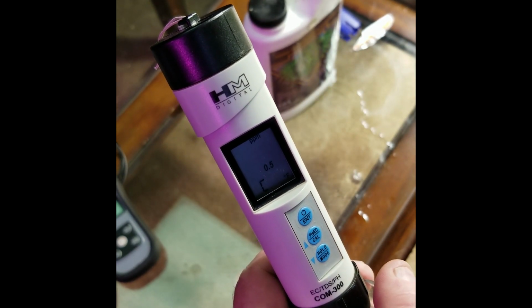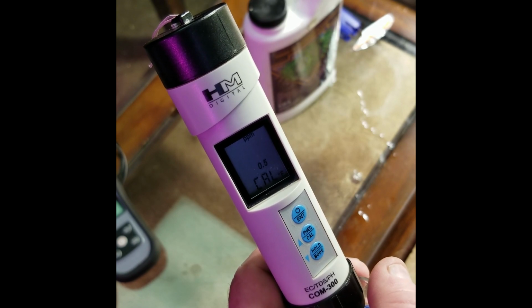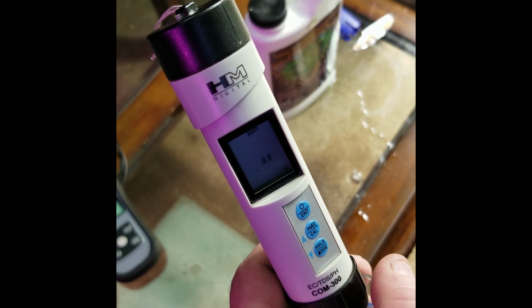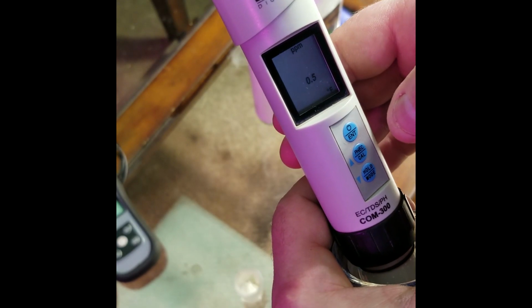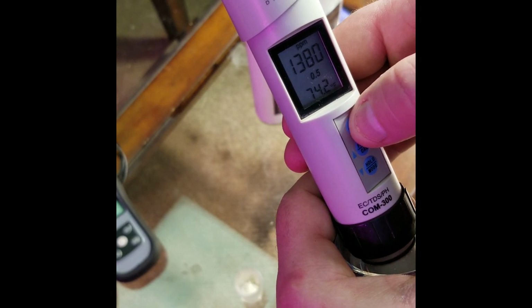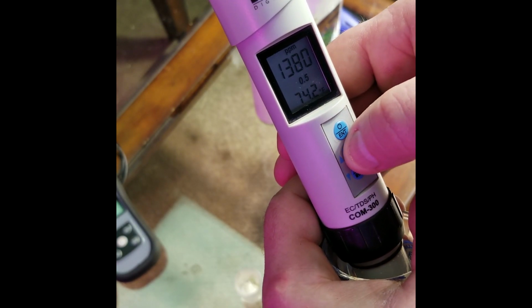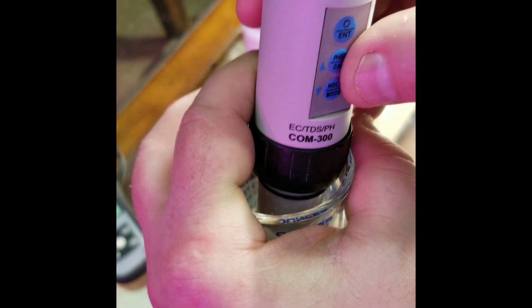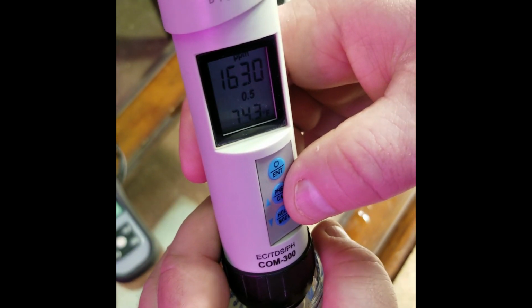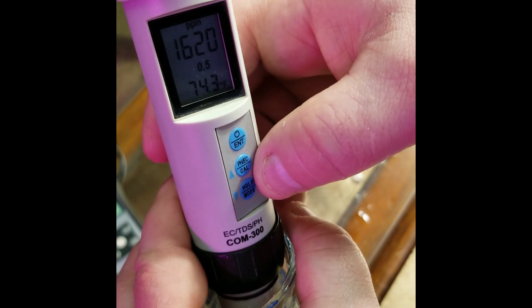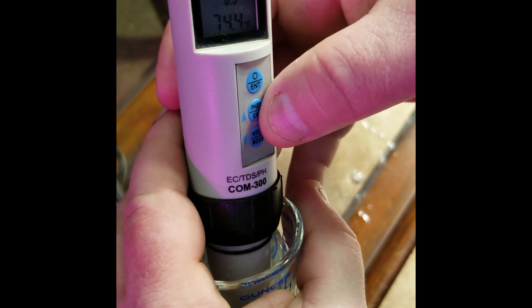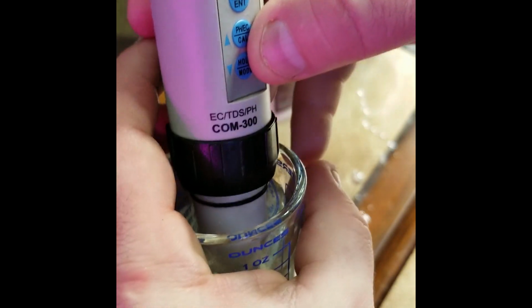It sits there and runs cal to make sure that that doesn't wildly fluctuate. It says end, and it says 1380 on the 0.5 scale, so I'm going to do it a second time. That was barely touching. Well, I guess it wasn't that bad. See, it says 1620. It should be 1380. So yeah, I don't think that I had full contact.